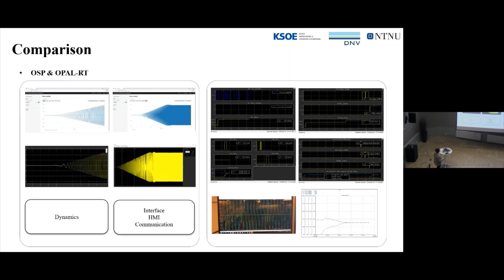And this is about results from the testing PMS. We can see the signal from PMS, such as start generator, connect, disconnect, and increasing speed for load sharing. We can see the load sharing was completed, controlled by PMS here, and my switchboard model also worked well. The synchronization logic was working to operate two generators at the same time in parallel.